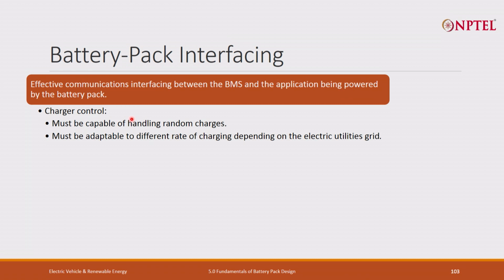If the charger is non-communicating, whatever the battery sends, if it is acceptable it will accept, otherwise it will reject. It won't allow the current to pass unless it is within the acceptable limit. A charger should be capable of handling multiple or random charge rates, but within the functional limit you have already set. If you have set the functional limit of 1C charge, then it should be able to take 0.5C, 0.7C, 0.2C, or even 0.01C.